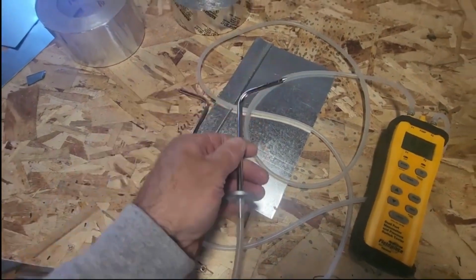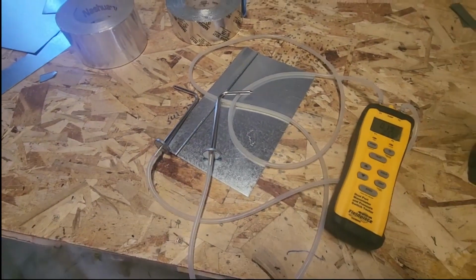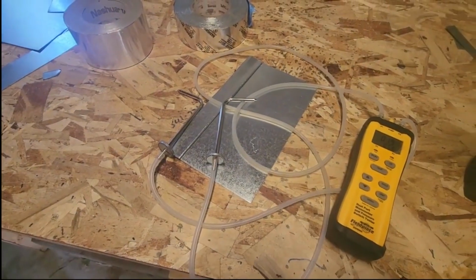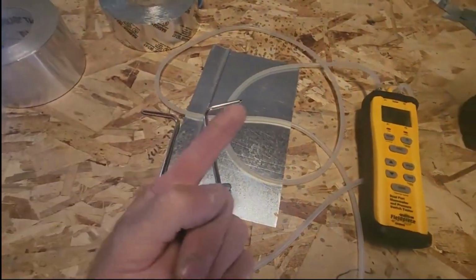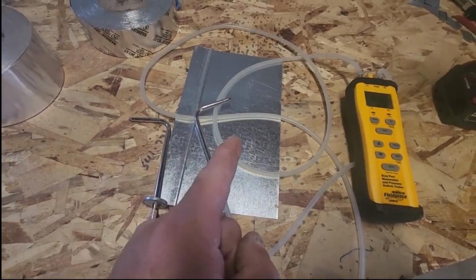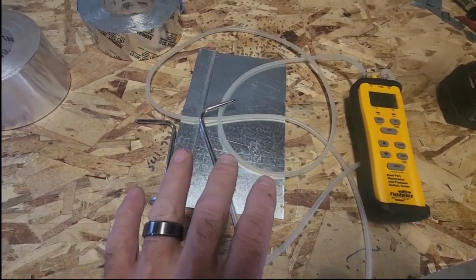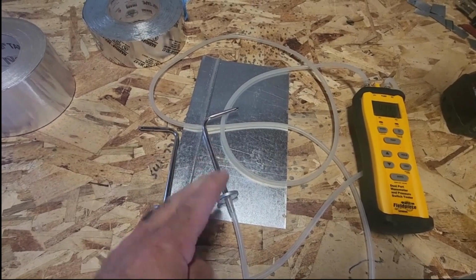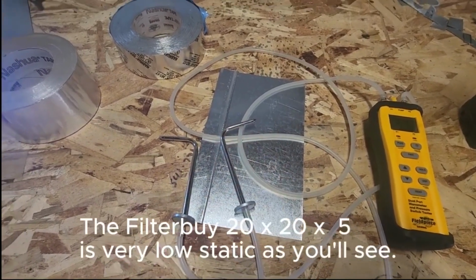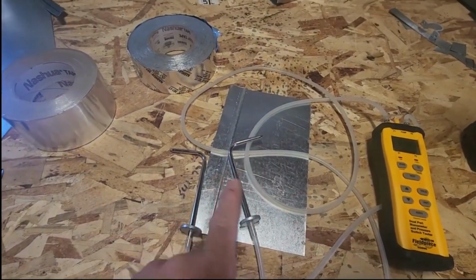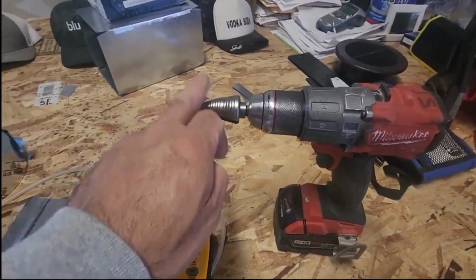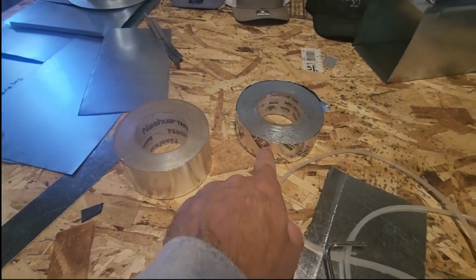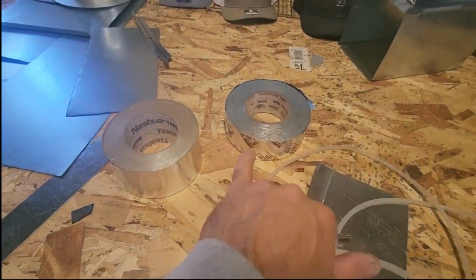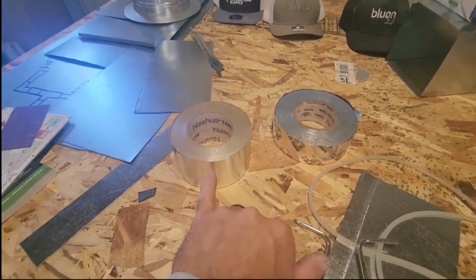This is going to be kind of interesting because I'm going to be able to show you total static pressure. I've got 2 zones on my zone system, so I'll show you what it's like with one damper open, one damper closed, and everything open. I'm going to do it with the filter in and the filter out, so you can see what kind of static pressure these 5-inch filters have. The last thing you're going to need is something to drill a couple of holes with. I also got tape to tape my holes. They make plugs, but it's my system, so I'll just tape my holes and tape my insulation back.